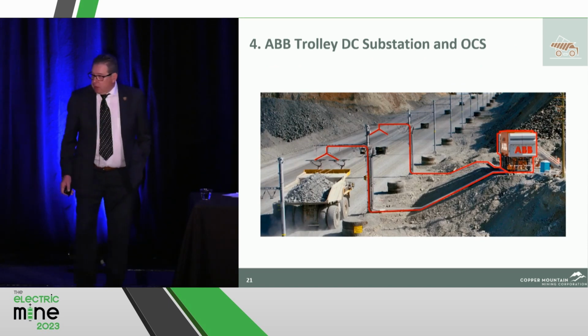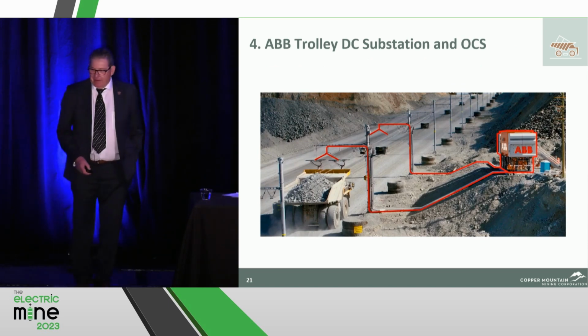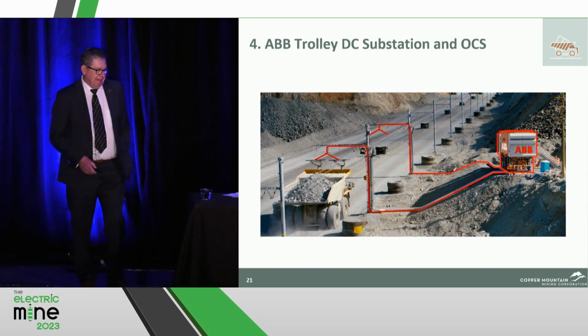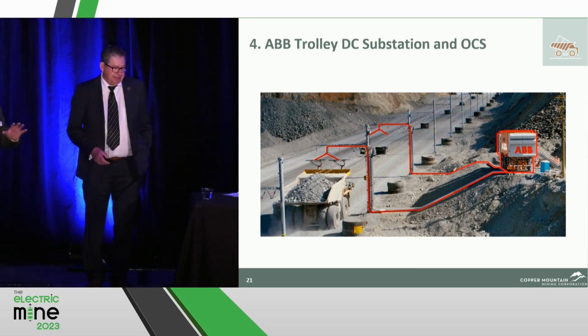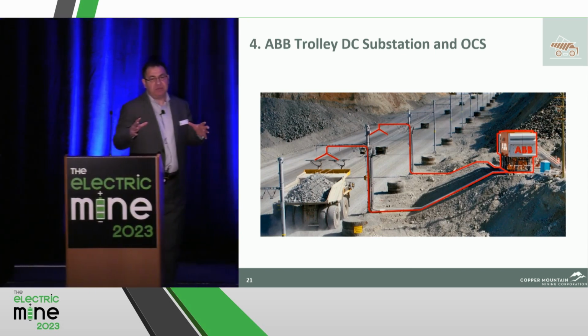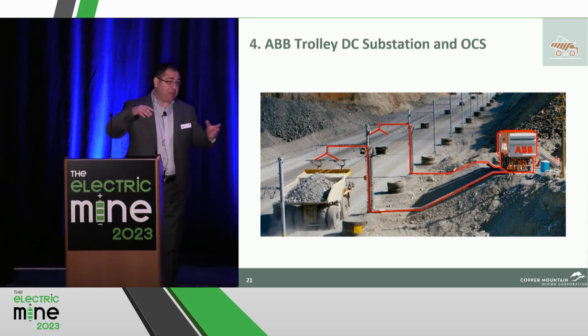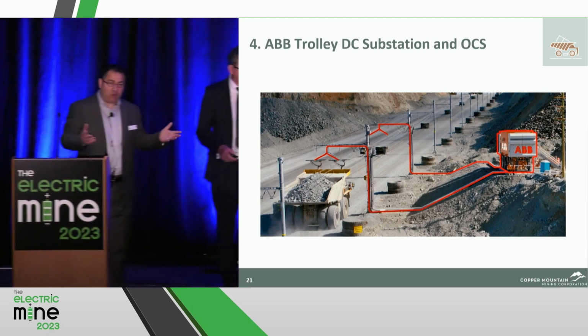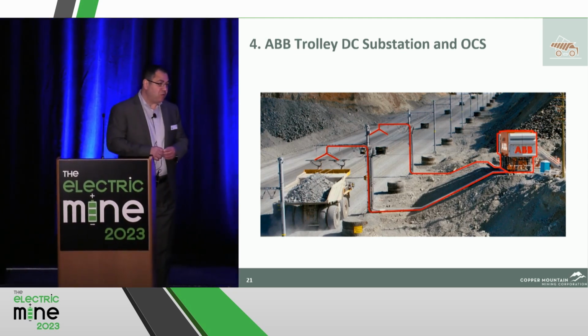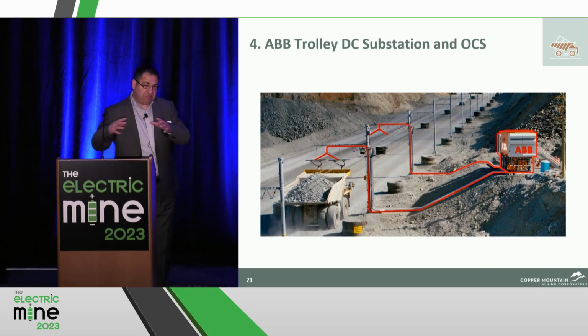So the ABB trolley substation, George, do you want to talk about that? I'll pitch in. So the power supply to the trolley has two main components: the DC substation that converts the AC coming from the 25 kV line to DC to power the trucks, and of course, the OCS, or the overhead catenary system.